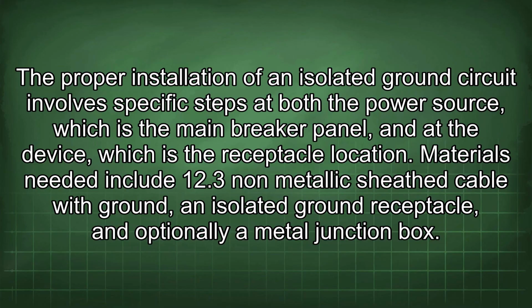Proper installation of an isolated ground circuit involves specific steps at both the power source, which is the main breaker panel, and at the device, which is the receptacle location. Materials needed include 12-3 non-metallic sheath cable with ground, an isolated ground receptacle, and optionally a metal junction box.